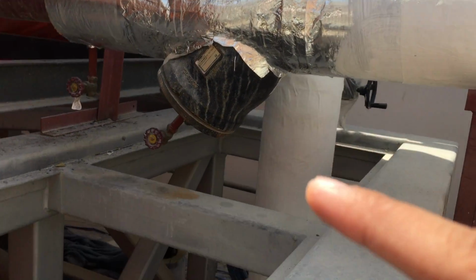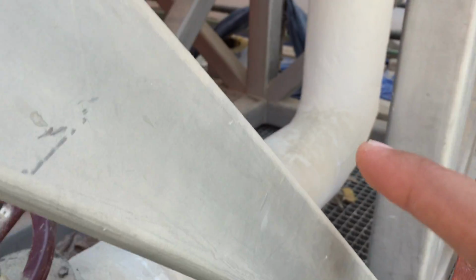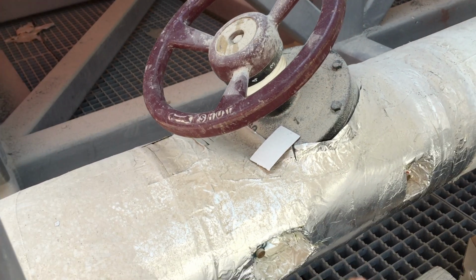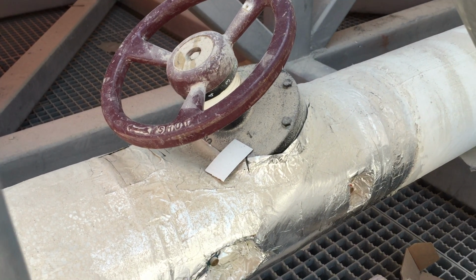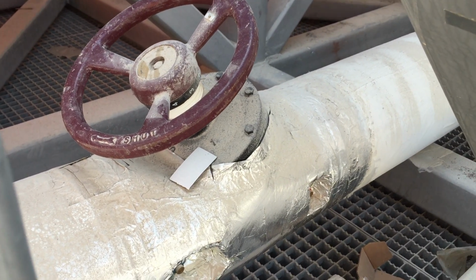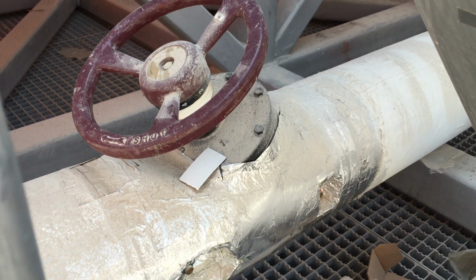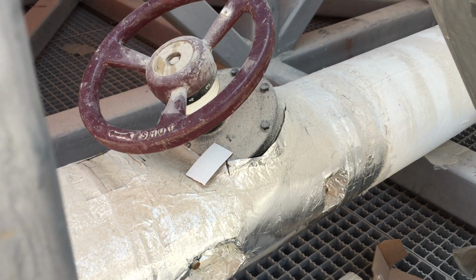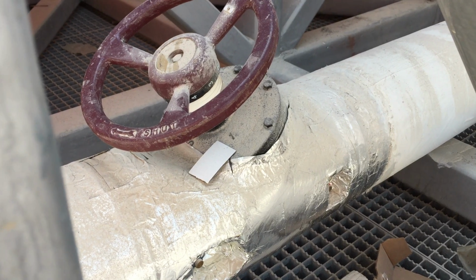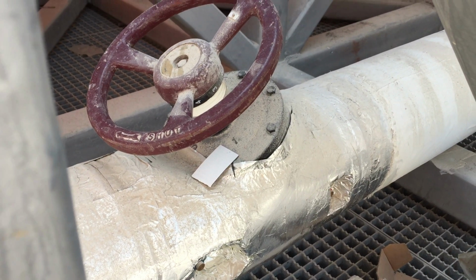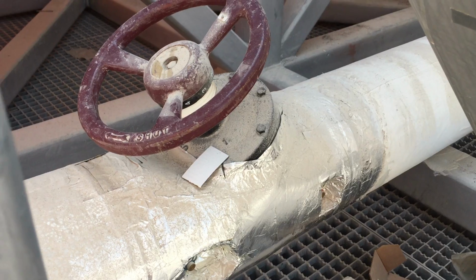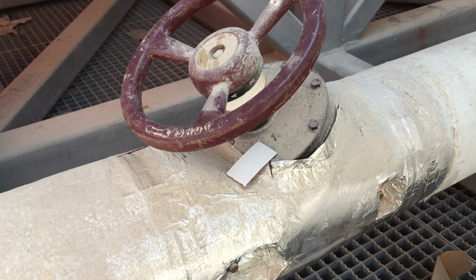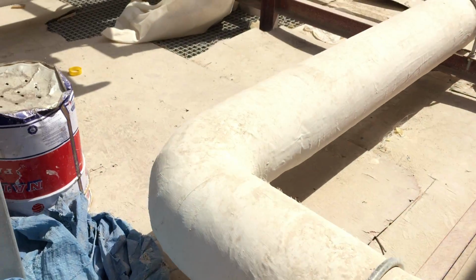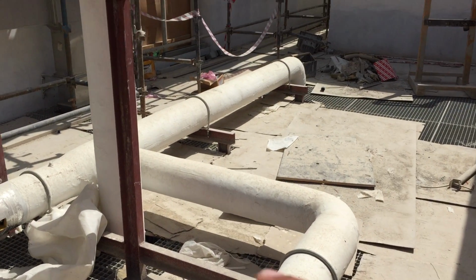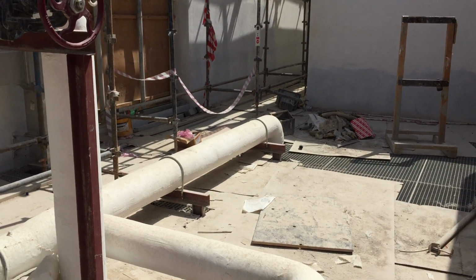Now this line is going from here, if you see it is coming down, and we have here DRV, double regulating valve. This is to control the flow of the chiller, what we have in the design. Suppose if we have 45 liters per second or something like that, whatever we have we can control with this DRV. Now this line is going to the system, or to the load.